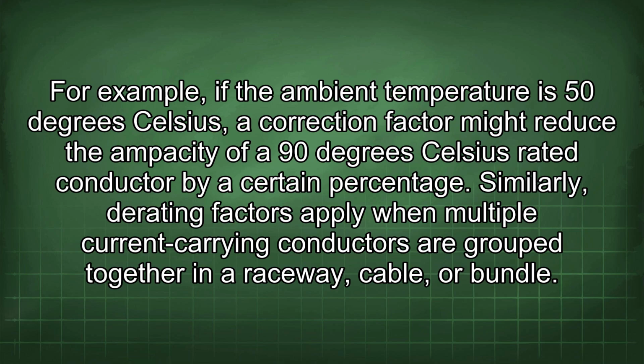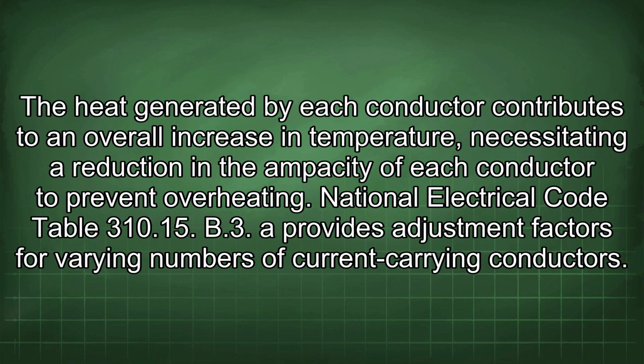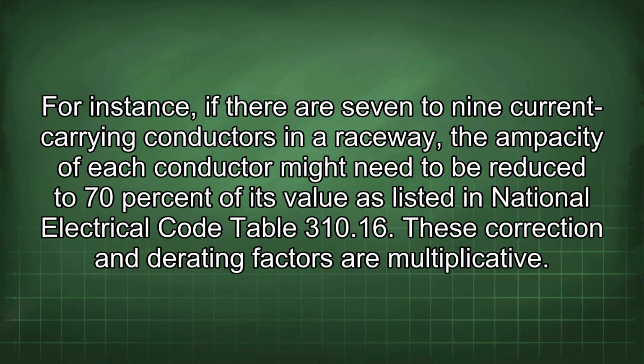Similarly, derating factors apply when multiple current carrying conductors are grouped together in a raceway, cable, or bundle. The heat generated by each conductor contributes to an overall increase in temperature, necessitating a reduction in the ampacity of each conductor to prevent overheating. National Electrical Code Table 310.15 B3 provides adjustment factors for varying numbers of current carrying conductors. For instance, if there are 7 to 9 current carrying conductors in a raceway, the ampacity of each conductor might need to be reduced to 70% of its values listed in National Electrical Code Table 310.16.